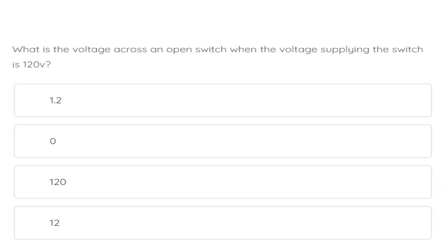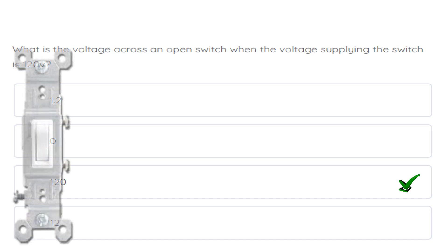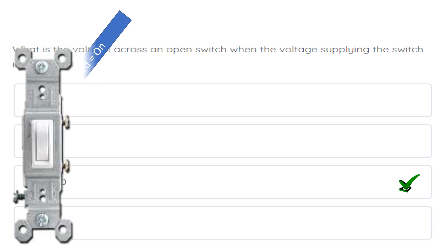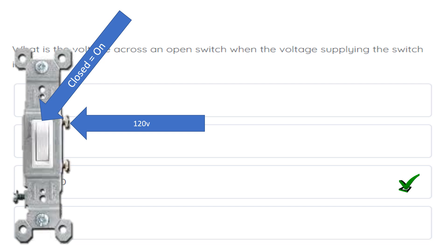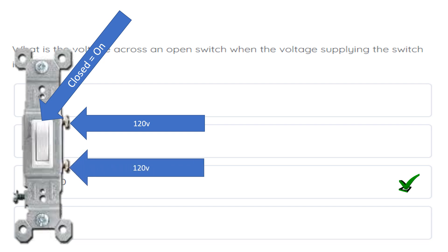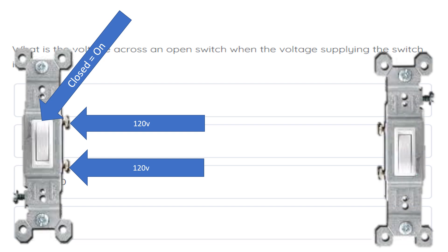What is the voltage across an open switch when the voltage supplying the switch is 120 volts? The correct answer is 120 volts. Let's imagine the switch is on — closed equals on. We have 120 volts on the top terminal and 120 volts on the bottom terminal, making the difference in potential zero. It's all about the difference in potential: 120 on top, 120 on bottom, so there is no difference.